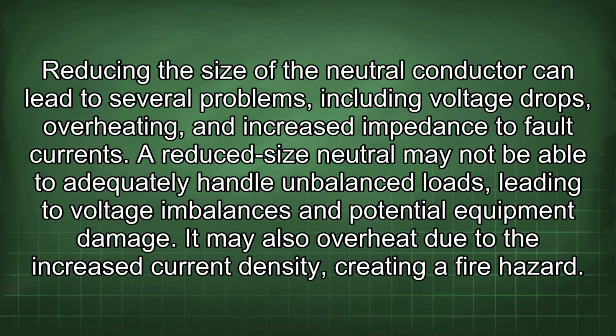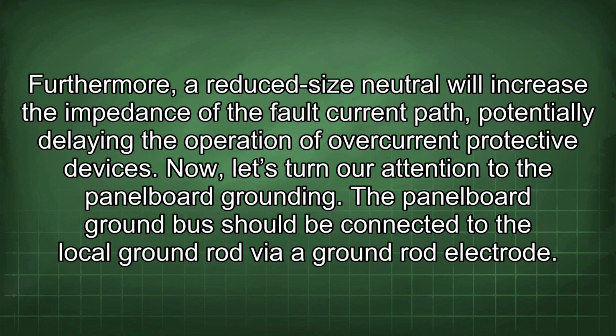Reducing the size of the neutral conductor can lead to several problems, including voltage drops, overheating, and increased impedance to fault currents. A reduced size neutral may not be able to adequately handle unbalanced loads, leading to voltage imbalances and potential equipment damage. It may also overheat due to the increased current density, creating a fire hazard. Furthermore, a reduced size neutral will increase the impedance of the fault current path, potentially delaying the operation of overcurrent protective devices.